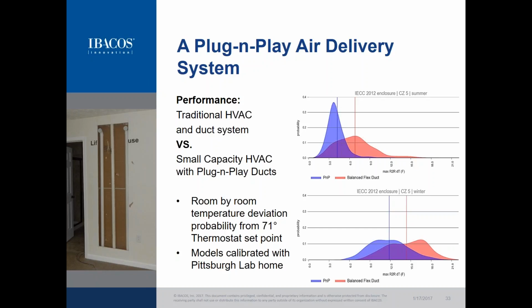And basically what we've achieved is the amount of time that the plug-and-play system stayed within the room temperature deviation, from room to thermostat, was a lot greater versus a similar flex duct system that is traditionally installed in the market.